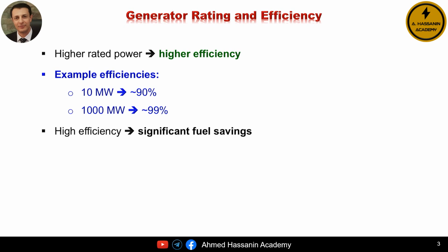To give you a practical sense of this, a synchronous generator rated at around 10 megawatts typically operates with an efficiency close to 90%. When we scale up to very large units, say 1000 megawatts, the efficiency can reach about 99%. That difference may look small on paper, but in real power stations, it is massive.